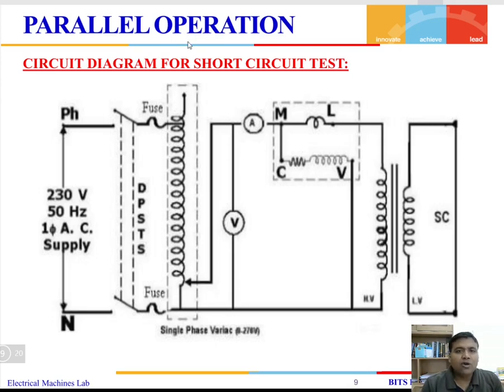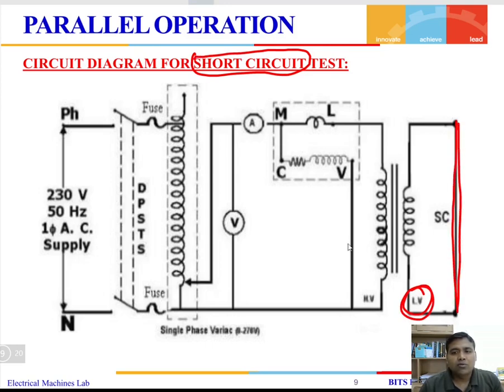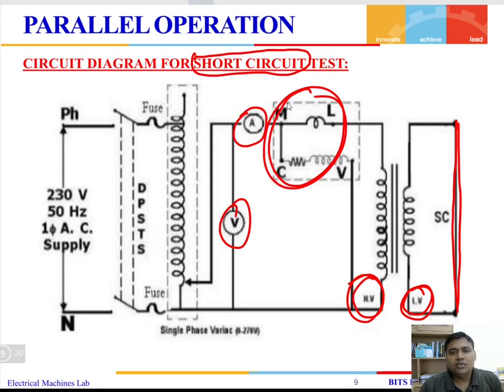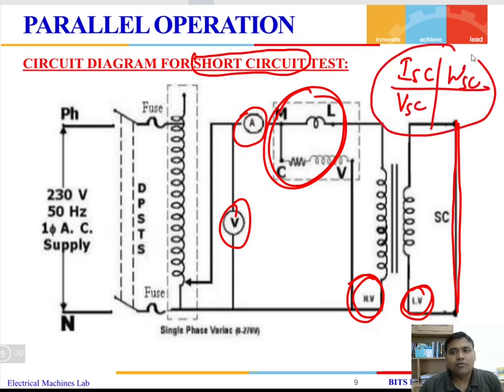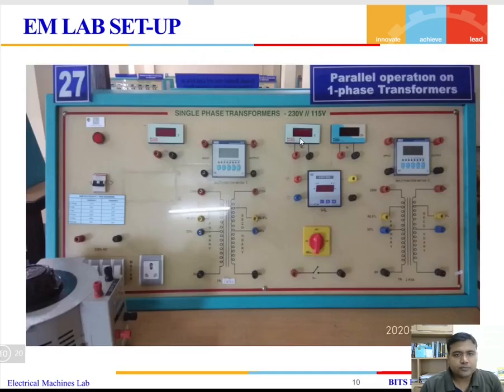Along with that, we have to perform a short circuit test on the transformer, which is also experiment number 10. On the low voltage side, we short the transformer, whereas on the high voltage side we connect all the measuring instruments, whether ammeter, voltmeter or wattmeter, and we measure the short circuit current, short circuit voltage and short circuit power. So three things we measure by performing the short circuit test.